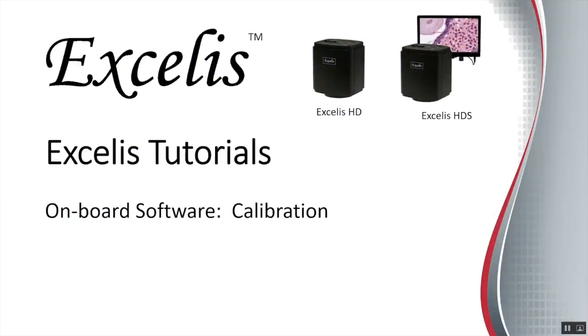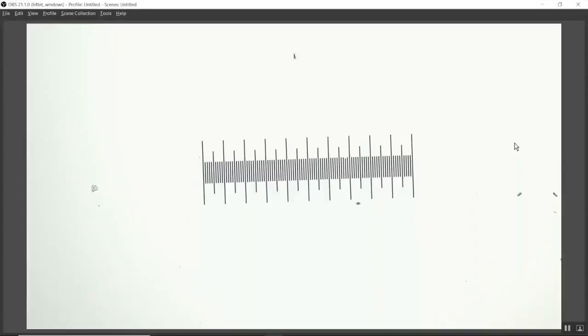In this next section of the Excelis tutorial, we'll show you how to calibrate your camera. In order to perform a calibration, you will need some standard device. I happen to be using a stage micrometer. The ruler that is on this micrometer measures 1 millimeter in length. Each division is 0.01 millimeter, which is equivalent to 10 microns. So the entire length of this scale is 1,000 microns, or 100 divisions. I move to my lowest magnification, which is 4x.